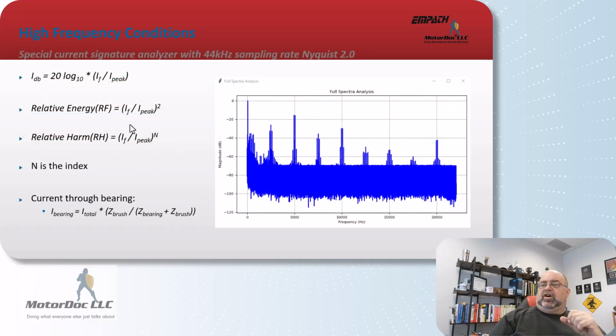So we take a look at all of that, and we take a look at the frequencies involved. So at about 5 kilohertz, we're at about 18 dB down, and at 20 kilohertz, we're at about 40 dB down. Believe it or not, those are equivalent. And at 10 kilohertz, something amazing happens. The brush, that's about where the brush becomes, well, when it switches, and I've got more current flowing through the bearing than I do through the brush.